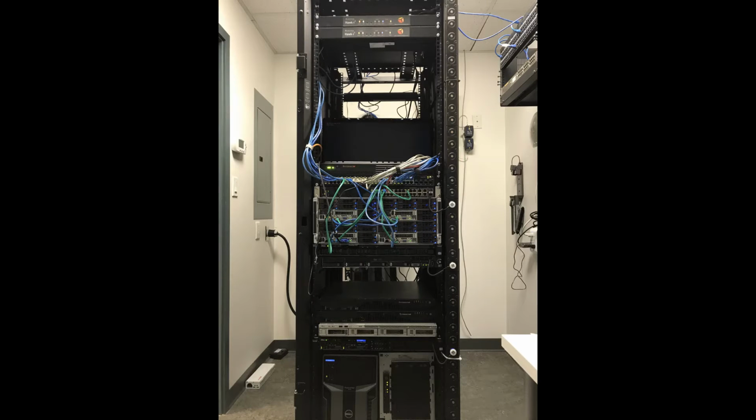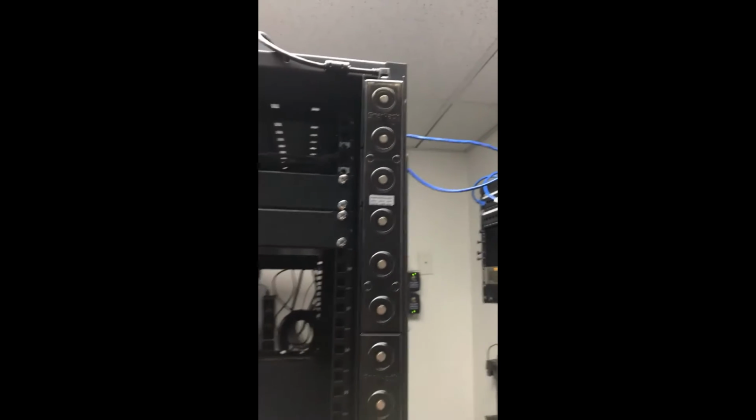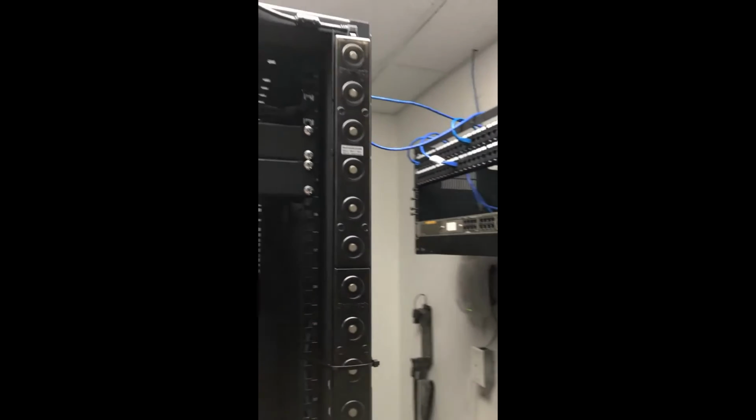Now I'll move to a hands-on demonstration of both the software and hardware. The AssetTracker modules can be mounted on either side of your rack in a number of different ways. They are secured by a variable length metal bracket, which can be screwed or zip tied in place. The modules are powered by a PoE, or Power over Ethernet, injector. They come in both 5U and 6U sizes to accommodate any rack height.